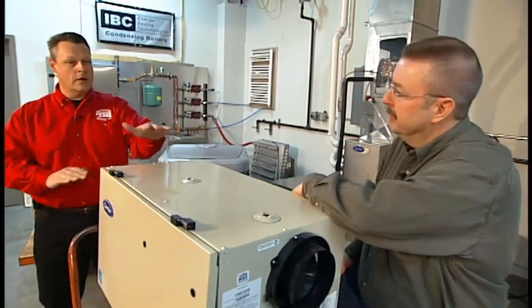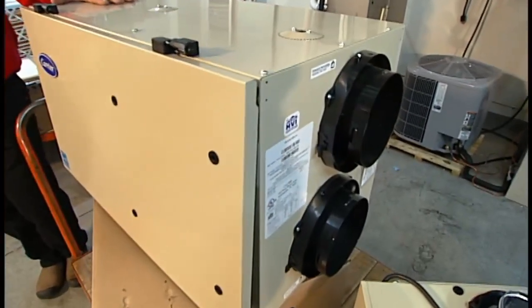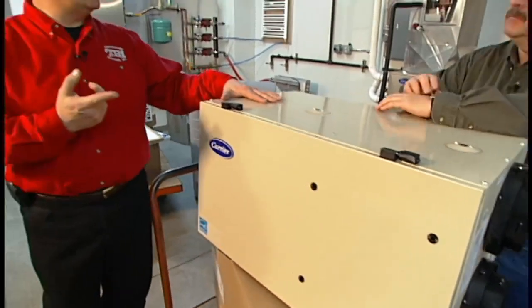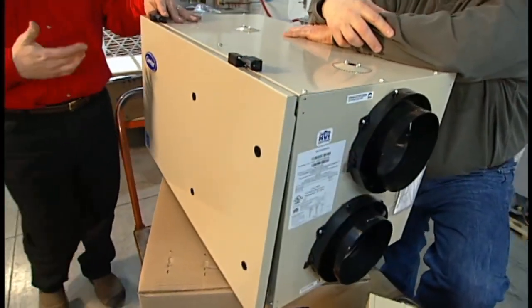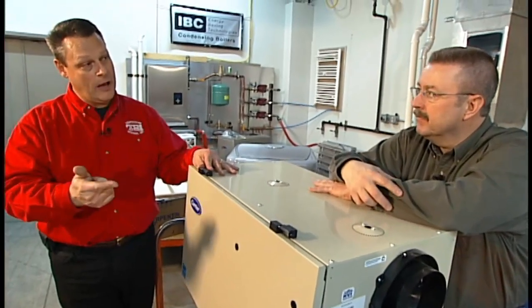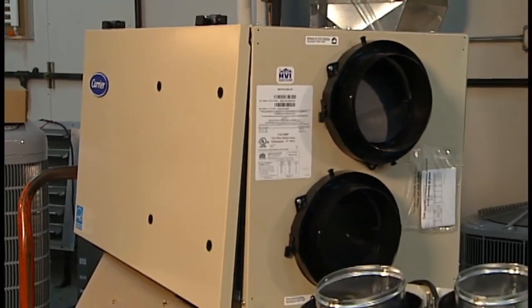To do it controllably, it's nice to use a product called a Heat Recovery Ventilator or an Energy Recovery Ventilator. Fresh air is needed, so you've got one of two ways — one is you cut a hole in the wall and introduce fresh air, which is counterproductive to increasing efficiency and lowering utility costs. This product will actually control ventilation on demand, turned on based on humidity and also on a runtime per day, so that while you're in the home you get a certain amount of CFM — cubic feet of air — moving through.